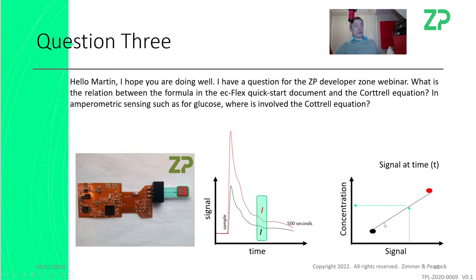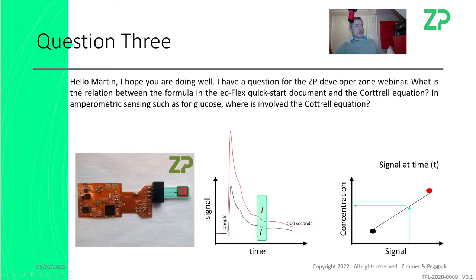Glucose strips have gone what's called calibration-free or code-free. But for years that batch calibration approach is what they were doing. To become calibration-free is a big investment — it took about 20 years. So if you have a Cottrell-type response, choose the time most indicative of concentration, create a calibration curve in a third-party system, and when you get a signal for an unknown sample at that time point, use the calibration curve to determine the actual concentration.